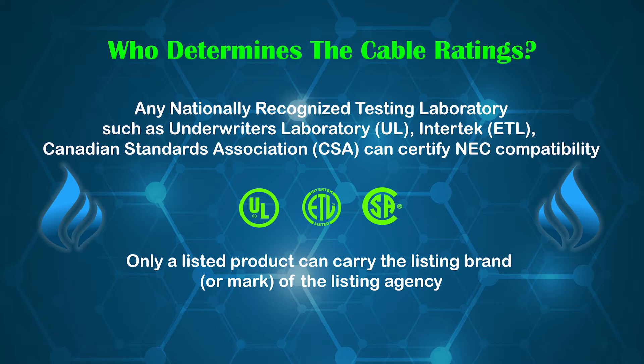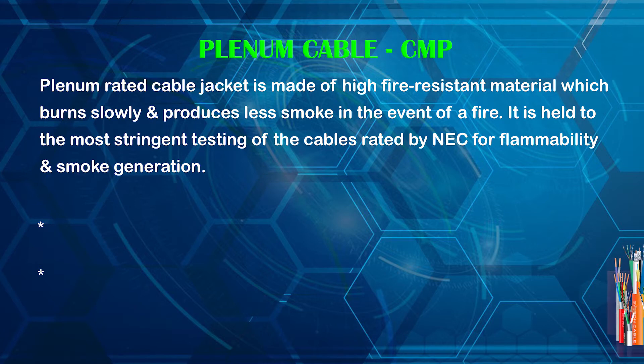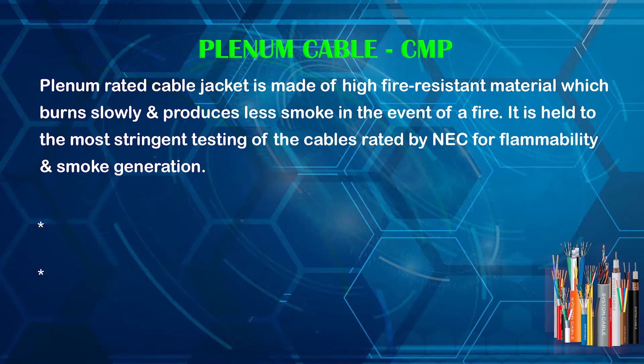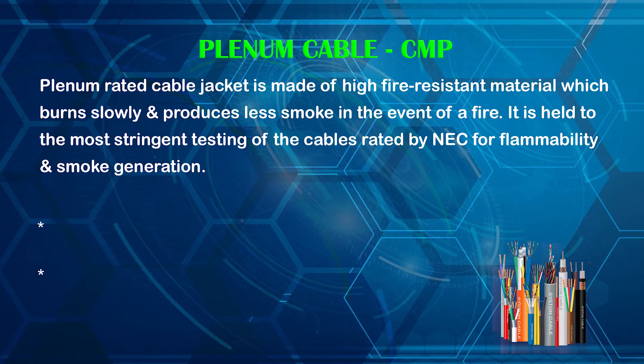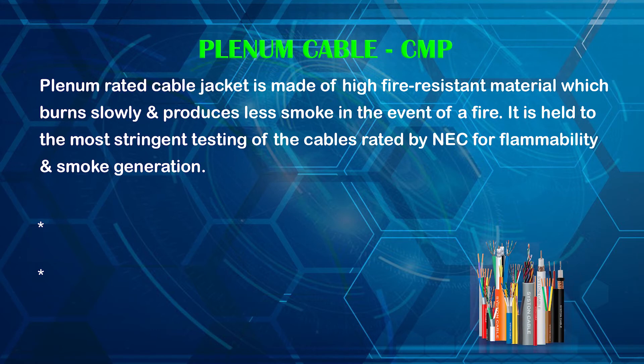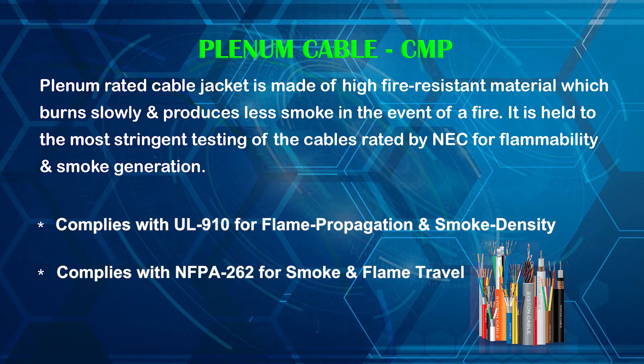Plenum rated cable jacket is made of high fire resistant material which burns slowly and produces less smoke in the event of a fire. It is held to the most stringent testing of the cables rated by NEC for flammability and smoke generation. Plenum rated cables should comply with UL 910 for flame propagation and smoke density, and also with NFPA 262 for smoke and flame.